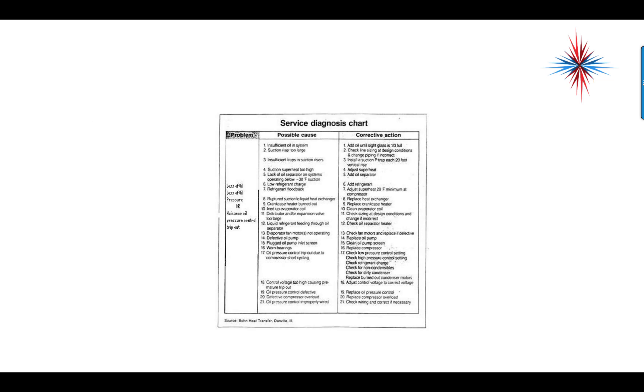There is a service diagnostic chart available that walks through all of this. Insufficient oil — add oil to the sight glass. Suction riser too large — check line sizing. Loss of oil pressure or nuisance oil pressure control trip-outs are a major problem in commercial refrigeration. They need to be corrected, and corrected properly the first time.